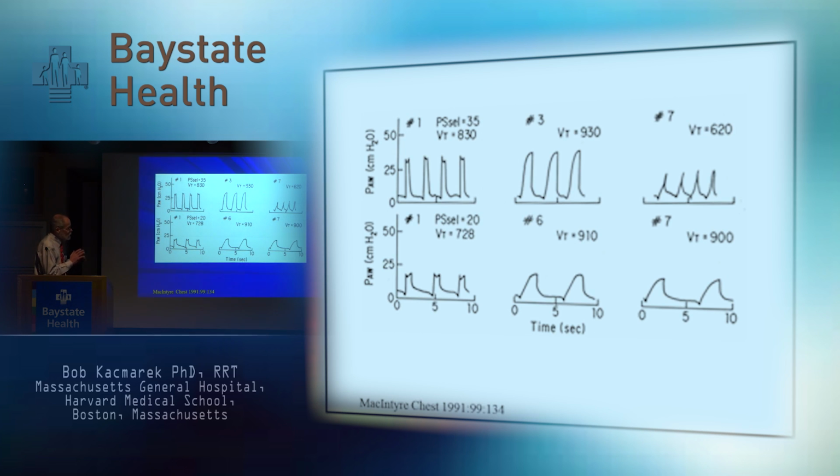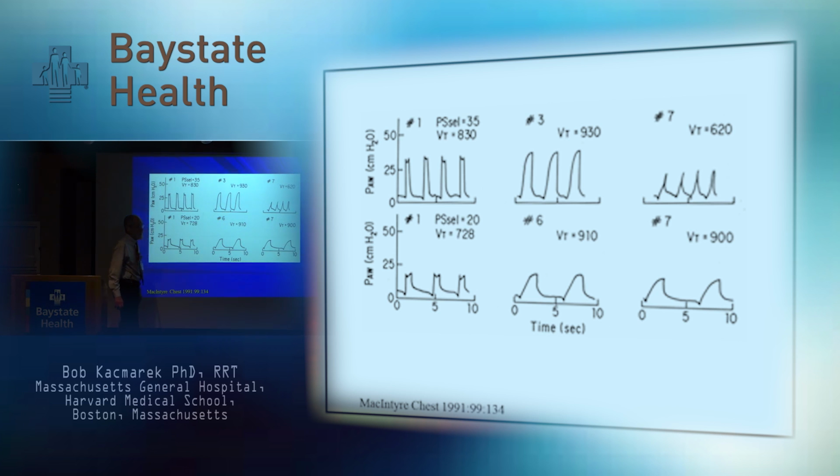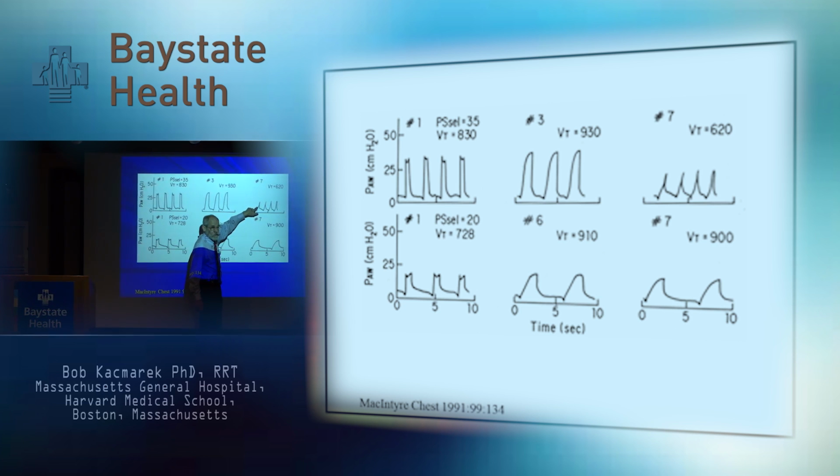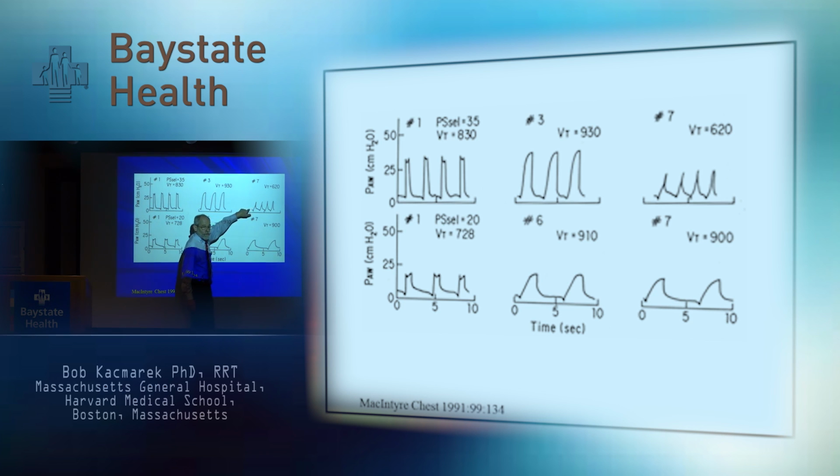In pressure-targeted ventilation, the same thing can happen. This is an old study, volumes way too large, by Neil MacIntyre. But the issue was to look at the way pressure ventilation was delivered and the use of rise time. With pressure ventilation, rise time adjusts the speed with which flow goes from 0 to the peak level. This was what they considered the optimal rise time, excessive rise time, minimal rise time, where you had the same concavity associated with volume ventilation because the flow was inadequate for this particular patient.